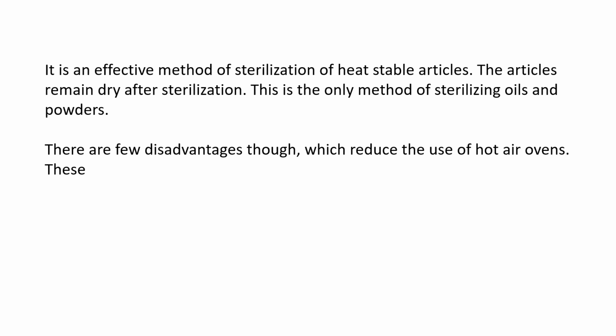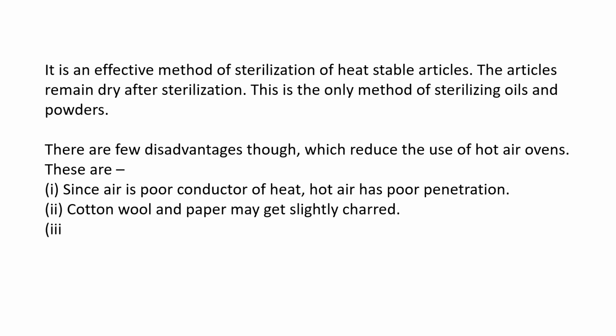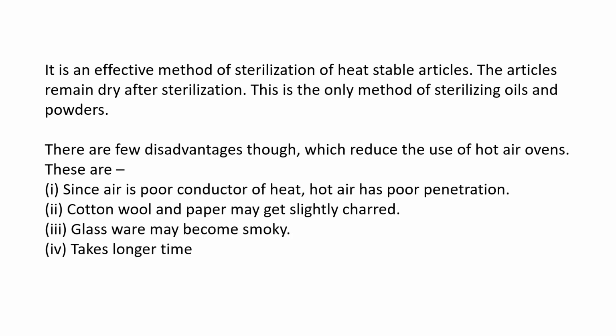However, there are a few disadvantages. These are, since air is a poor conductor of heat, hot air has poor penetration. Cotton wool and paper may get slightly charred, glassware may become smoky, and it takes longer time compared to autoclave. Let us now move on to moist heat.